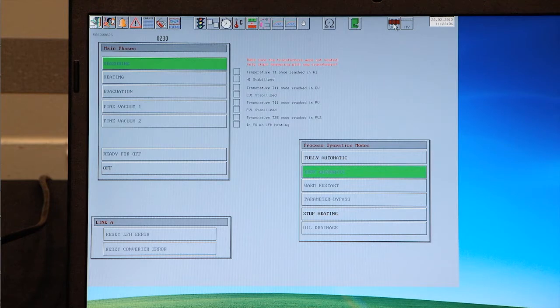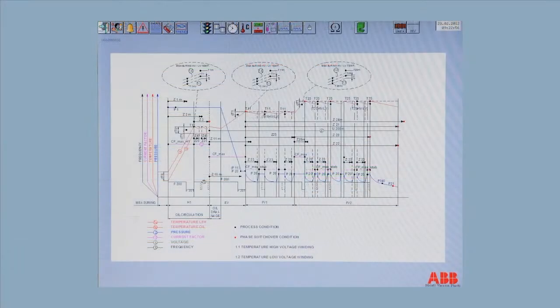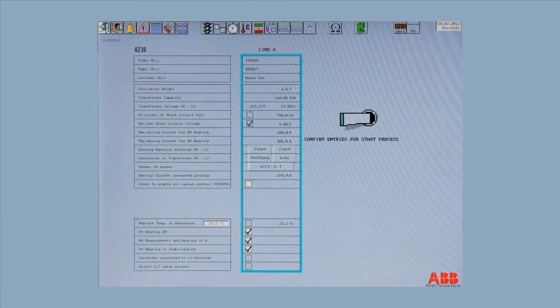with the oil plant needs manual actions where it can be of benefit that the plant does not automatically transit between the stages. On a transformer that is at ambient temperature, start the process by clicking on Measuring, which is located on the 230 process screen. The control system checks the input data and the process will automatically start in the measuring step. If some conditions are not fulfilled, the process will not be possible to start. Recheck all of the parameters, enter corrected transformer values, and correct any wiring errors in this case.